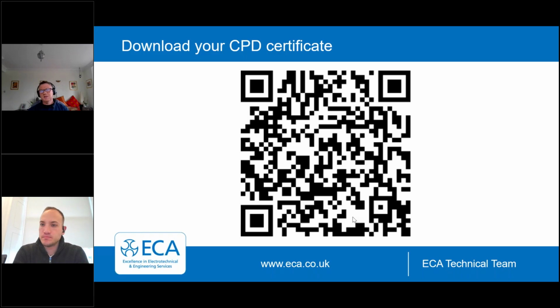But potentially, I know that's a bit of a sit on the fence, but it does depend on a few issues. If you've got any specific requirements, just email me or Roma, and I'll be happy to help you with those if need be. It does depend on how big it is, and where you're placing the other emergency lighting in that area. And the design of the cubicle as well. If the wall goes right up to the top and there would be no natural light into the cubicle, then yes. But if the cubicle doesn't go up to the roof, it's not necessarily as straightforward as you might think.